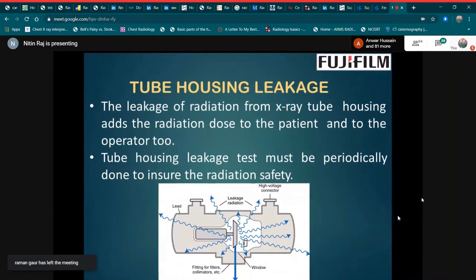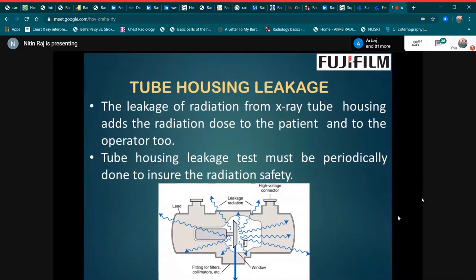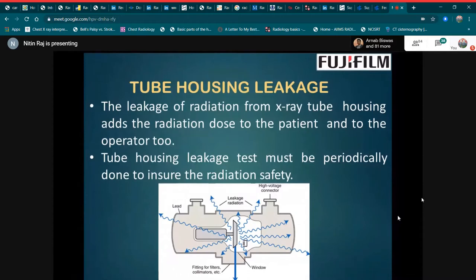Next is tube housing leakage. Leakage of radiation from the x-ray tube housing adds to the radiation dose to the patient and to the operator. Tube housing leakage tests must be periodically performed to ensure radiation safety.